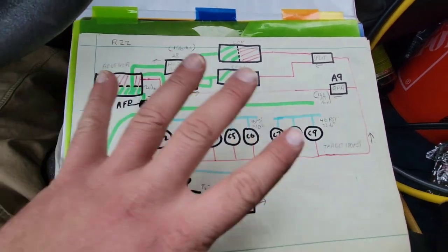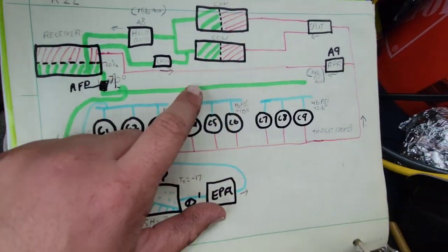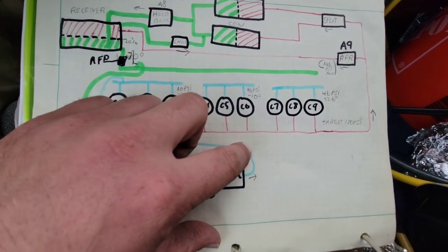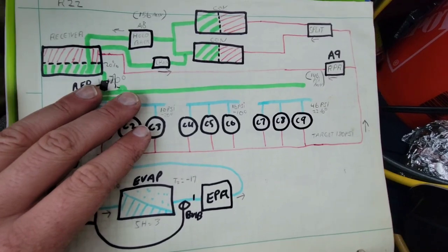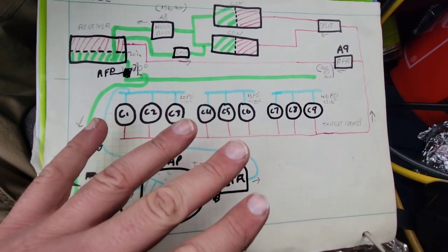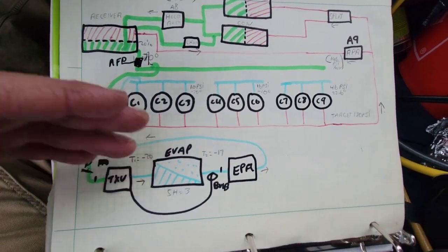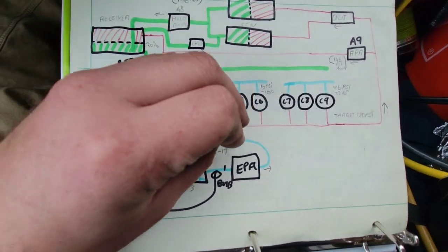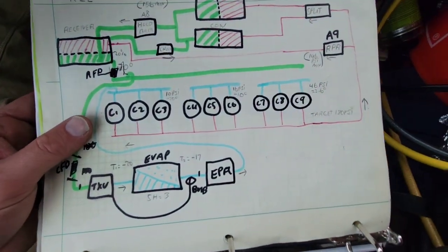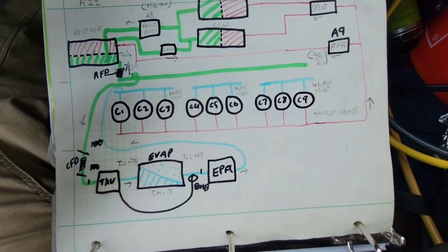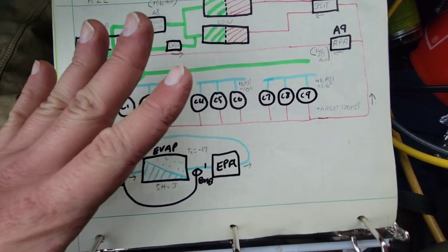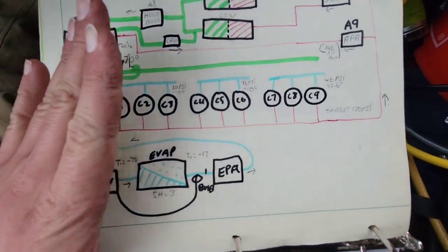Before we go up and check the other stuff at the rack, while we're at the controller, I just want to interject this. We have to make sure that the controller is calling for refrigeration to begin with. Typically the controller would send voltage to an EPR, or a suction line solenoid or something, in order to get the system flowing. We want to make sure the actual computer says, yes, I am trying to refrigerate, before we move to the next step and troubleshoot, because we need to know that. For instance, there could be offsets put in, or manual overrides put in or left in that technicians have done before, and we have to verify that quickly before we can move on.